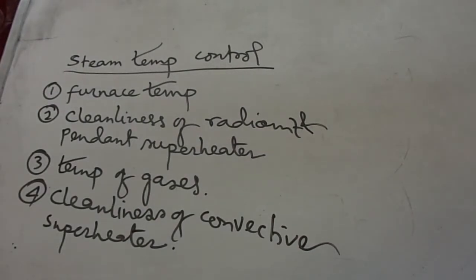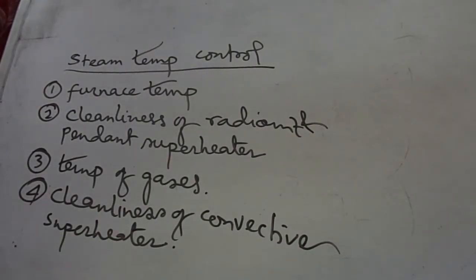Okay, cleanliness of convective superheater. Variation of load on the unit. These variables are not unrelated, but interrelationships among them are not simple. The last one, the effect of load variation on superheat temperature, is, however, the most important.